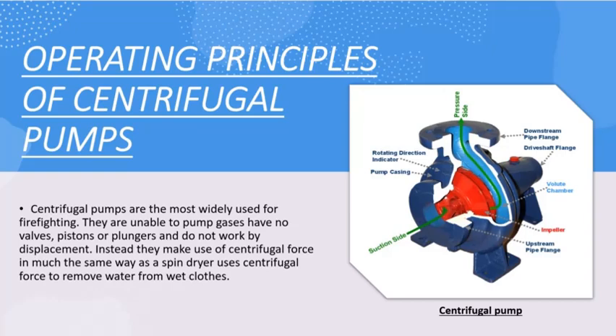The next type is the centrifugal pump, which is currently the most widely used type of pump in fire service. The main parts include the impeller — here you can see a closed type impeller — which is a rotor used to increase the kinetic energy of the flow. There is also a volute casing, which contains the liquid and acts as a pressure containment vessel that directs the flow of liquid in and out of the centrifugal pump.